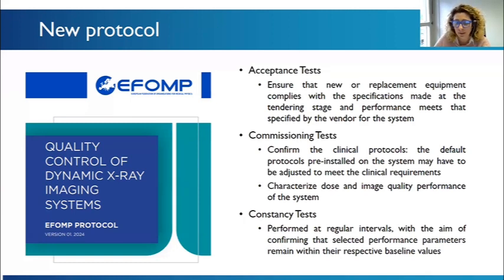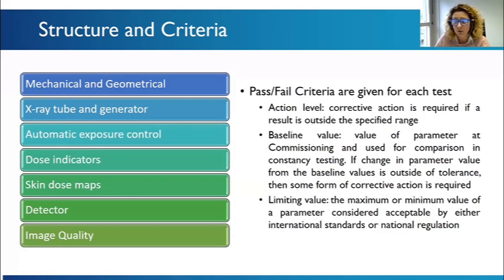It includes some acceptance tests, commissioning tests, and constancy tests. That's the terminology we use. So acceptance tests are to be performed at the beginning, just to verify that your system is fulfilling the documentation that you required during the tender. Commissioning tests are to set the baseline. This is the heaviest part of the protocol. And constancy tests verify the performance of your equipment over time.